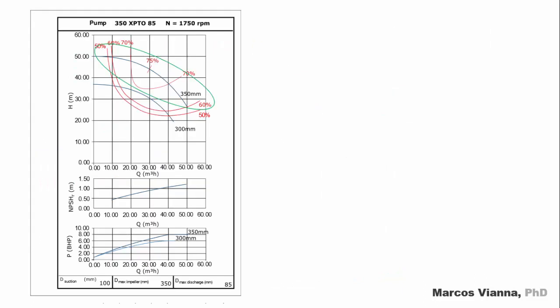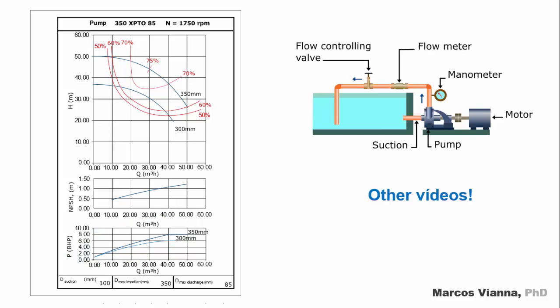Until we complete the curve. This is how the pump manufacturers obtain the curves that will be given to you. Of course, they will run tests like this for all the required impeller diameters of a given pump. Other tests are also important to fulfill the chart of the pump, such as the determination of its efficiency, its required net positive suction head, in short NPSH-R, and the power that it will require. But these are topics for other videos.